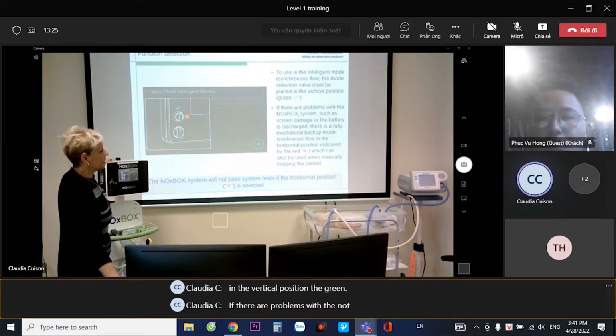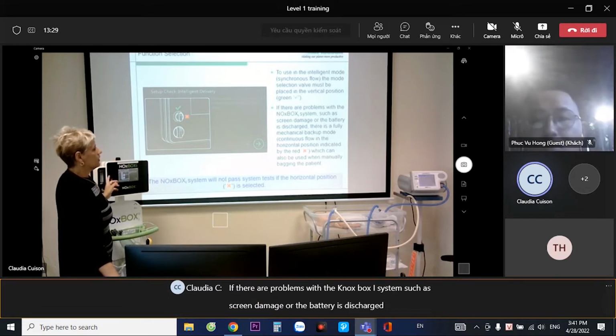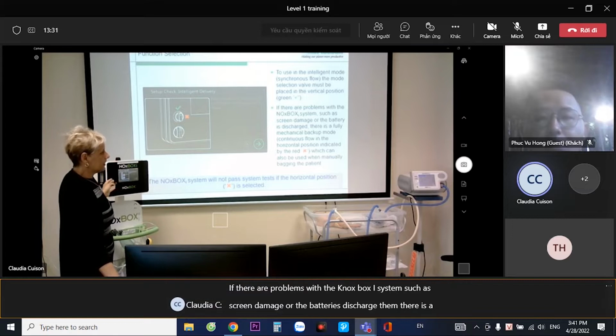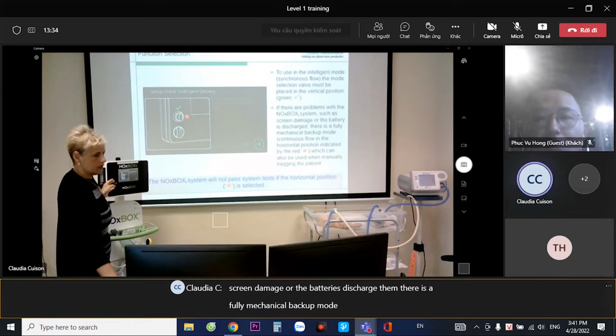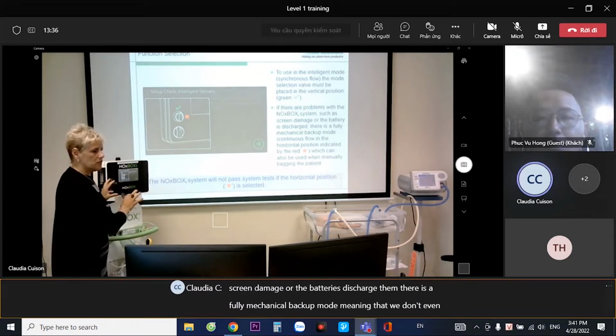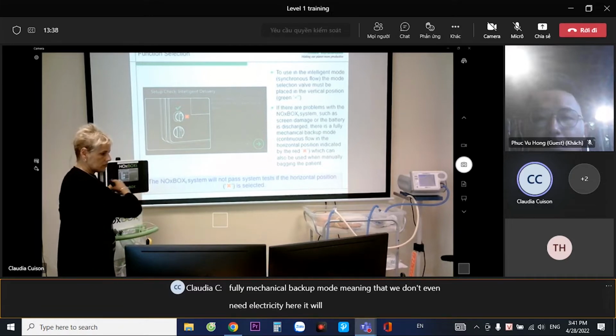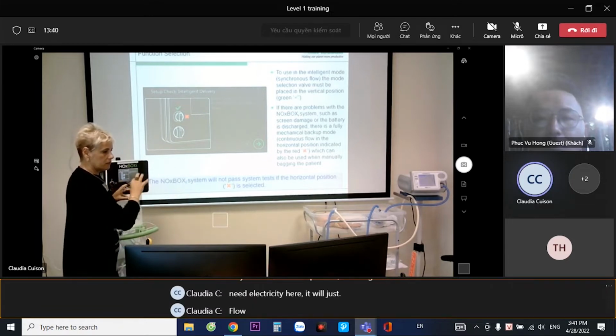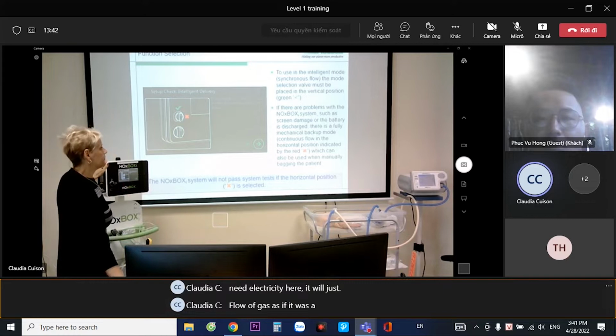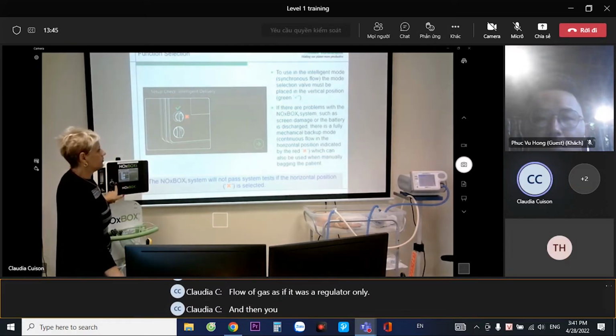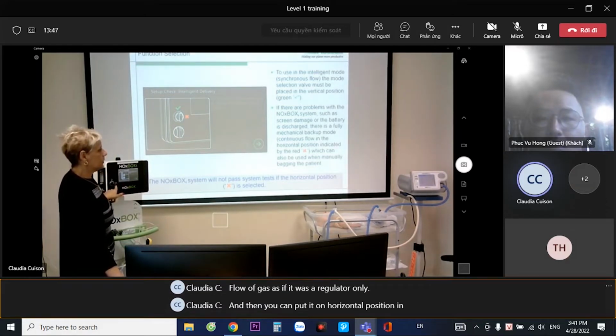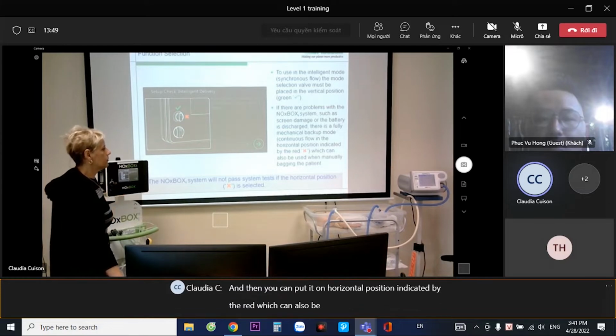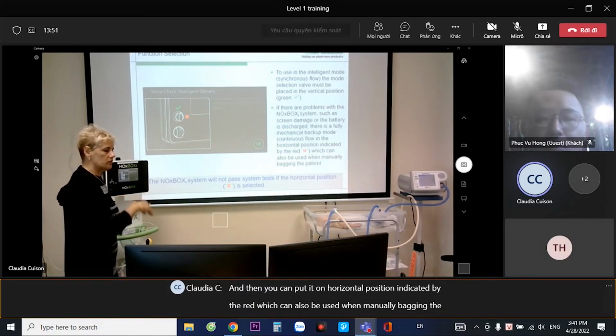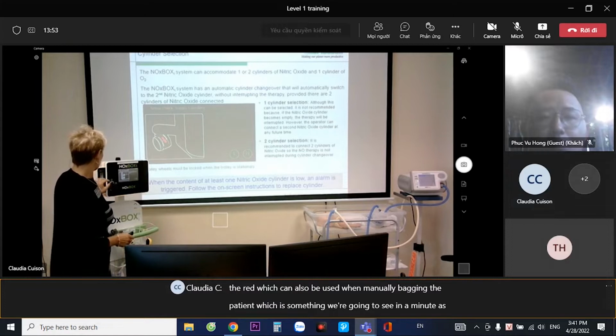If there are problems with the system, such as screen damage or the battery is discharged, then there is a fully mechanical backup mode, meaning that we don't even need electricity here. It will just flow gas as if it was a regulator only. Then you can put it in the horizontal position indicated by the red, which can also be used when manually bagging the patient, which is something we're going to see in a minute as well.